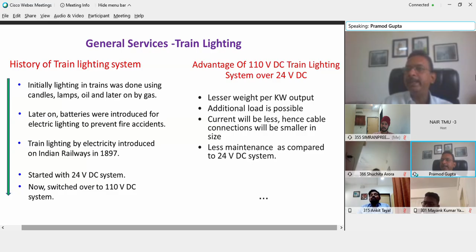The current will be less, hence cable connections will be smaller in size. As I increase the voltage level, for the same amount of power I require less current to be drawn, so I can afford the conductor size to be smaller, and therefore the connections will be smaller too. The fourth advantage is less maintenance compared to the 24 volt DC system, which was an old, obsolete design with no R&D or technical inputs being given. As a result, the generating equipment used in the 24 volt DC system was maintenance prone, whereas the 110 volt DC system requires less maintenance.